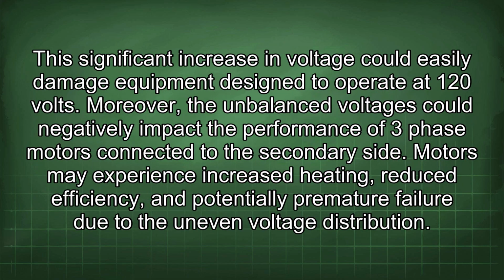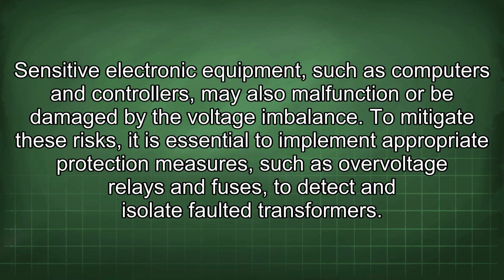This significant increase in voltage could easily damage equipment designed to operate at 120 volts. Moreover, the unbalanced voltages could negatively impact the performance of three-phase motors connected to the secondary side. Motors may experience increased heating, reduced efficiency, and potentially premature failure due to the uneven voltage distribution. Sensitive electronic equipment, such as computers and controllers, may also malfunction or be damaged by the voltage imbalance.